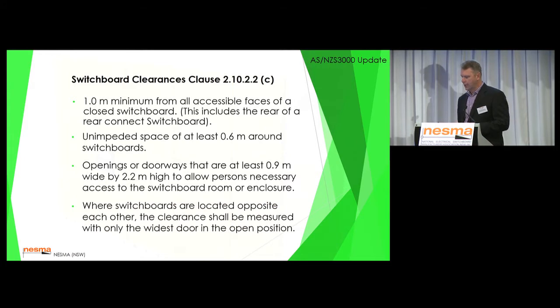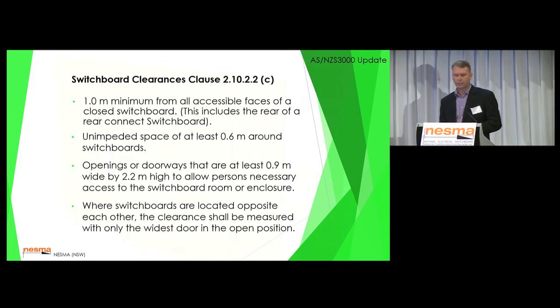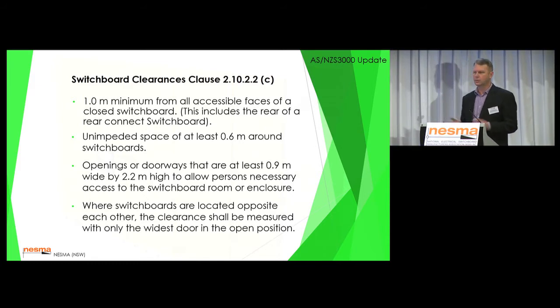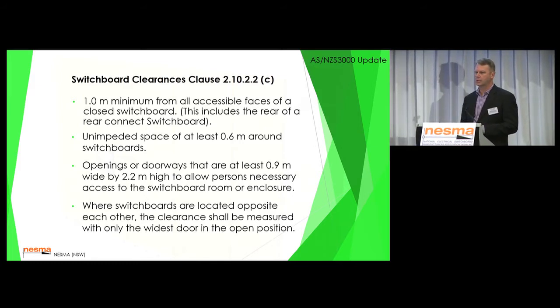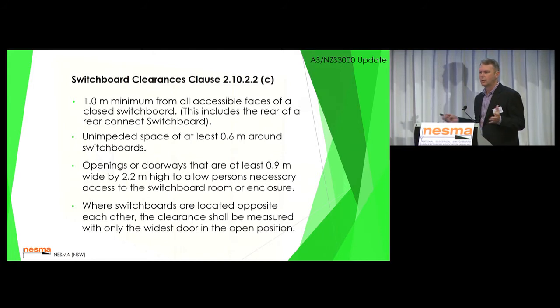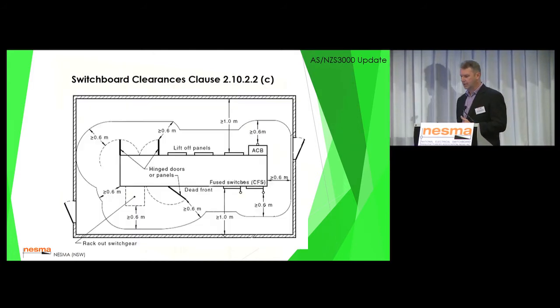Where switchboards are located opposite one another, the clearance shall be measured with only the widest door in the open position. This is always a bone of contention in previous standards, where it wasn't clear whether you had to open two doors facing each other. And we'll just have a look at some of these diagrams that are now in the standard.